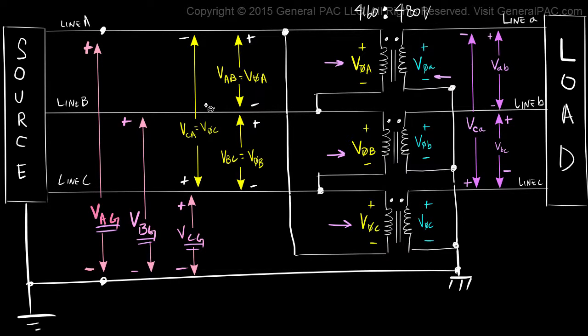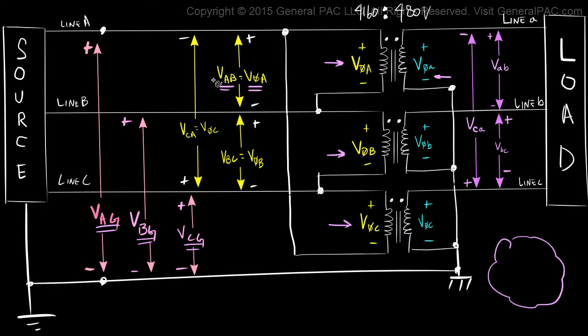Now line-to-line voltages are a little bit tricky. On the delta side, the high voltage side, the line-to-line voltage across line A and B is labeled VAB, which is also equal to the voltage across winding A, or Vphase A. If you are having a hard time understanding this, just click on the link where we talked about it in the previous tutorials. The line-to-line voltage across line B and line C is labeled VBC, which is also equal to the voltage across winding B on the high voltage side. And lastly, the voltage across line C and line A is labeled VCA, which is equal to the voltage across winding C.